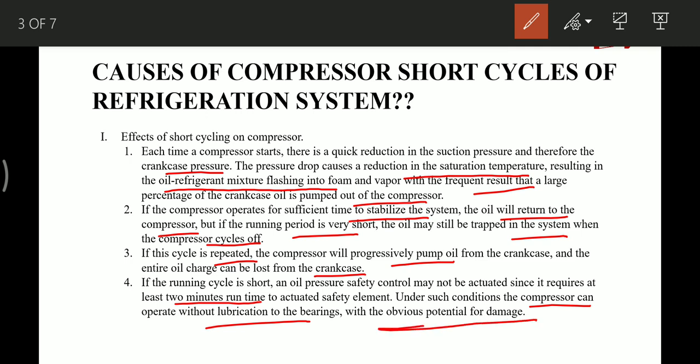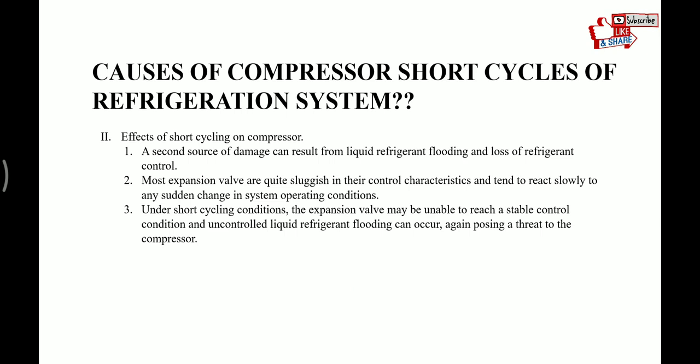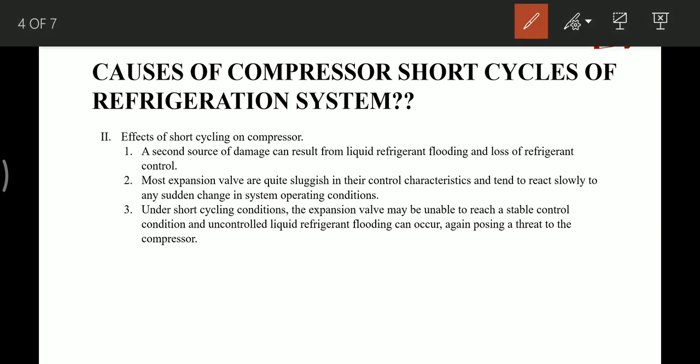Another effect of short cycling is that it can lead to liquid refrigerant flooding, and this liquid refrigerant can enter into the compressor. Most expansion valves are quite sluggish in their control characteristics. They need time to get stabilized, meaning they react very slowly to sudden changes in the system.